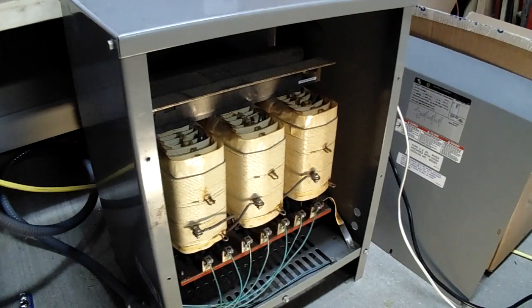So to get started, I'm going to show you the taps on the transformer, give y'all a close-up of that, and we can continue by rearranging the wires in such a way that we get a star-star transformer. So to start with this, as many of you may know, or may not know, transformers are dumb. And what I mean by that is, whatever voltage you put into it, it'll either double it or it'll half it, depending on which way you put it through. So if this is a step-down transformer, which it is originally intended for, then I can put 480 volts in and get 240 or 260 out, depending on how you have the taps wired. But if I put 260 in the secondary side, then out of the primary side I'll get 480 volts, and that's pretty cool.